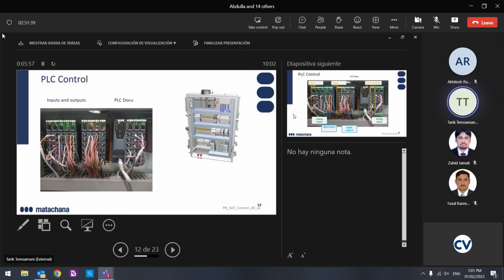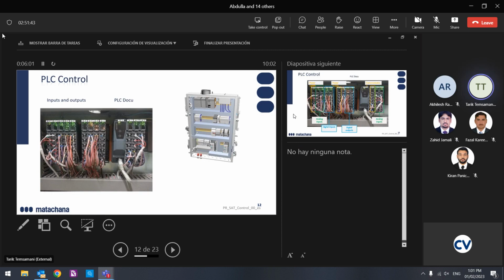PLC. Here we have two PLCs. Yes, we have one PC, but two PLCs. I will explain it. The left one is for control, basic, and the right one for documentation. That means in this machine we have every control twice. We have two temperature sensors for the chamber, two pressure sensors. Everything is two. One for the control and the other for the documentation, because we are always comparing the temperature and the pressure. If there is a difference between them, then I have a problem.